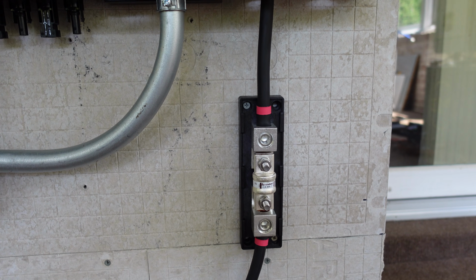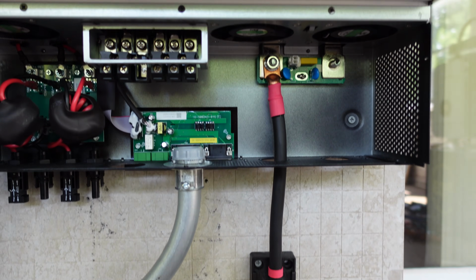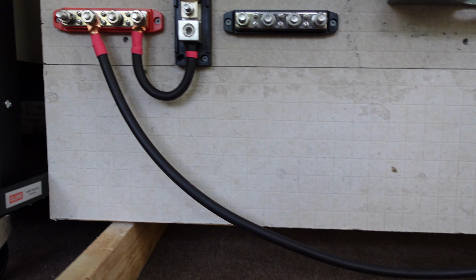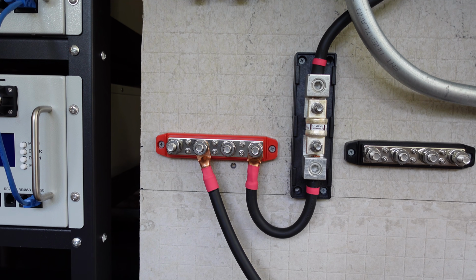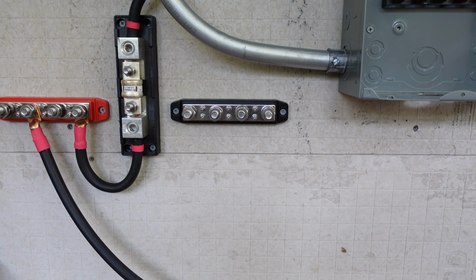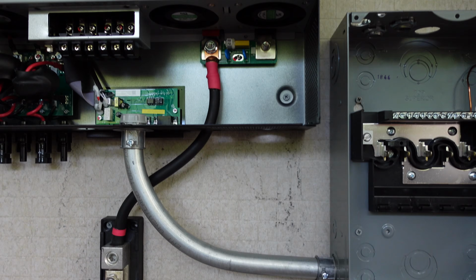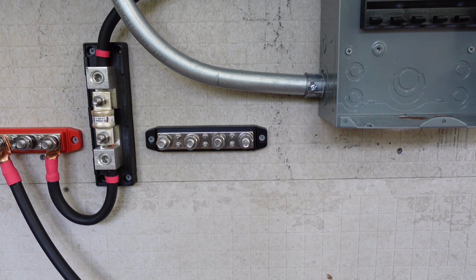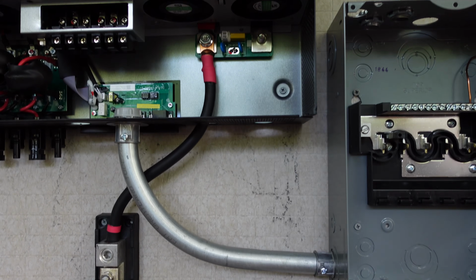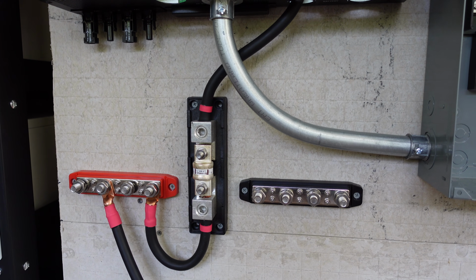So on the right hand side, the fuse block is connected to the inverter the same way, and then we have a long positive conductor that comes down and goes over to the bus bar on the left hand side. And we're going to wire the negative connection up to the inverter the same way. The only difference is we'll just go straight from the bus bar to the inverter. We won't have a fuse block on the negative conductor.